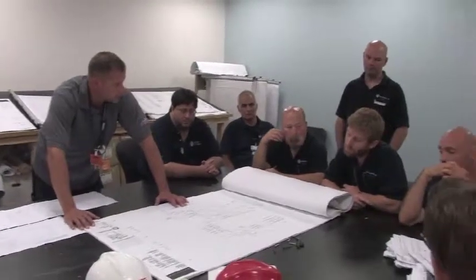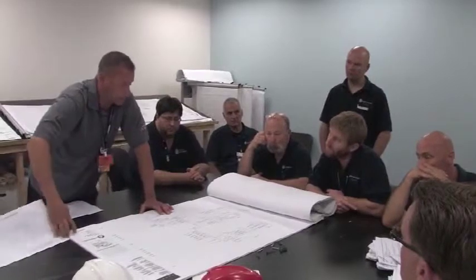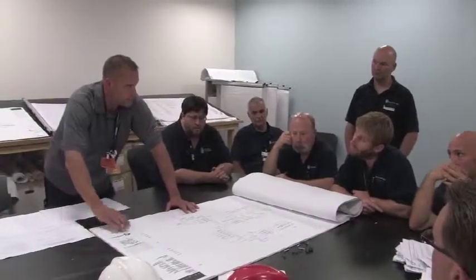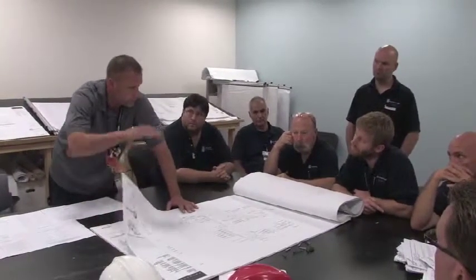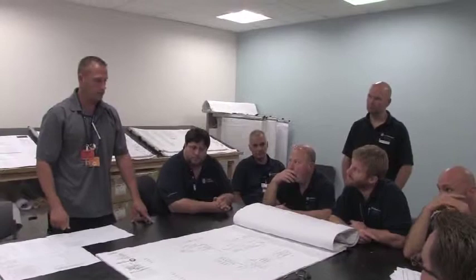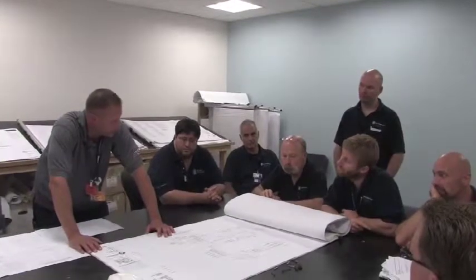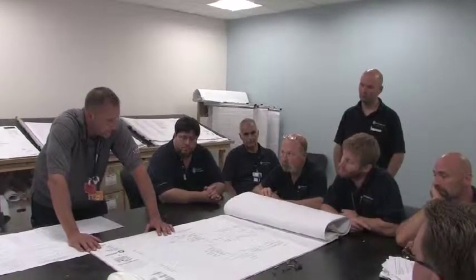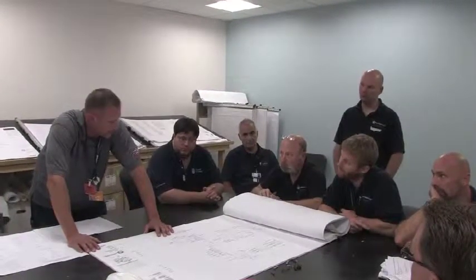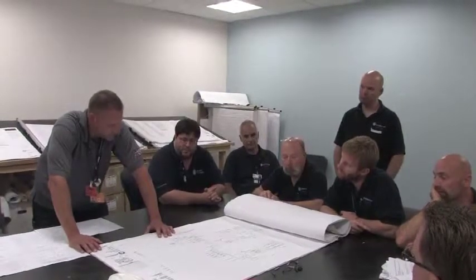As the liquid level depletes, it's going to be replaced with glycol. Yeah, there's pressure switches on the chemical feeder. So when it drops below a certain PSI, but it shouldn't, but if it does, it will make up. But it's going to make it up straight glycol. Okay. It's actually 40%. Oh, it's pre-mixed. It's pre-mixed. It's in the tank up there. Okay, cool. There's a tank full up there in the feeder. Okay. 55-gallon drum, or? No, it's in the feeder itself. Okay. Yeah, it's about 50 gallons, I think.